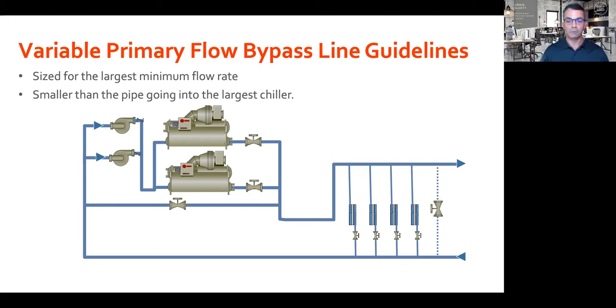If you're having issues with your plant or maybe experiencing what is referred to as a low delta T syndrome, and you know where your bypass line is located, you may look into the sizing of that pipe and valve. So confirm all the minimum flow rates. Next slide, please.